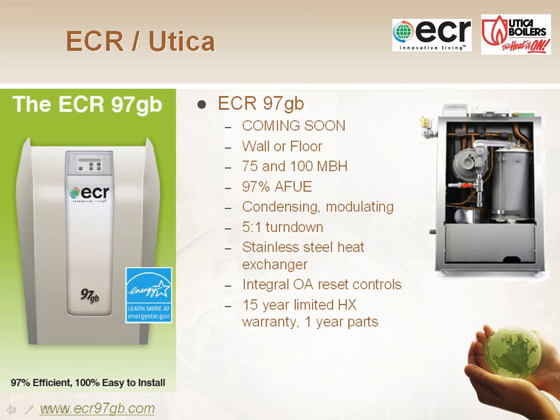However, we don't have to do the primary secondary piping. And the reason we don't have to do that is because, I don't know if you can even see in this picture up here, but there's a small Grundfos pump right there. Inside this boiler, there's already a pump and a small little primary loop. So physically inside the cabinet, there's already a primary loop. So when you stick this in the field and put it on your secondary loop, when you put a pump on it, it's already set up to do that.